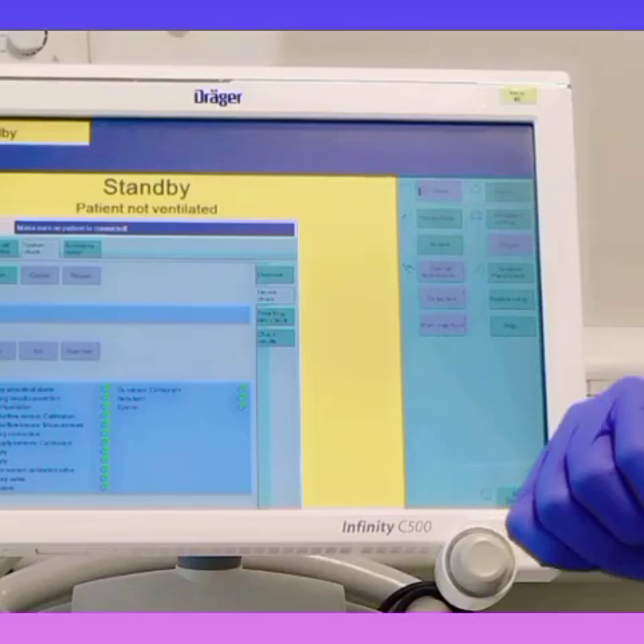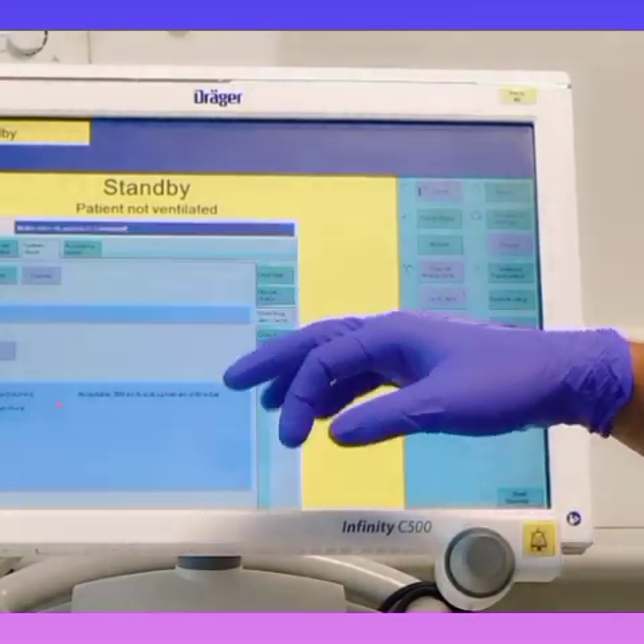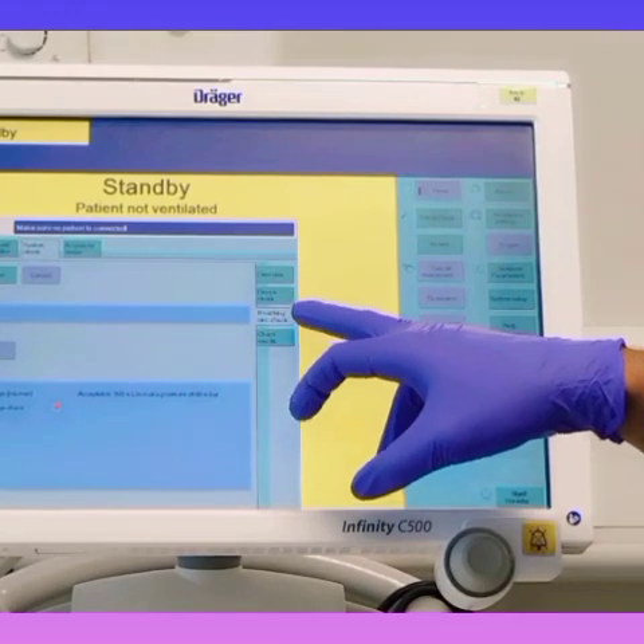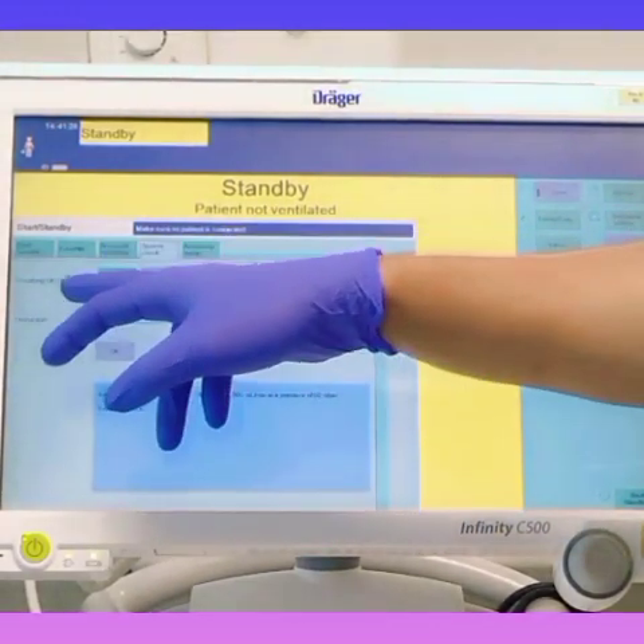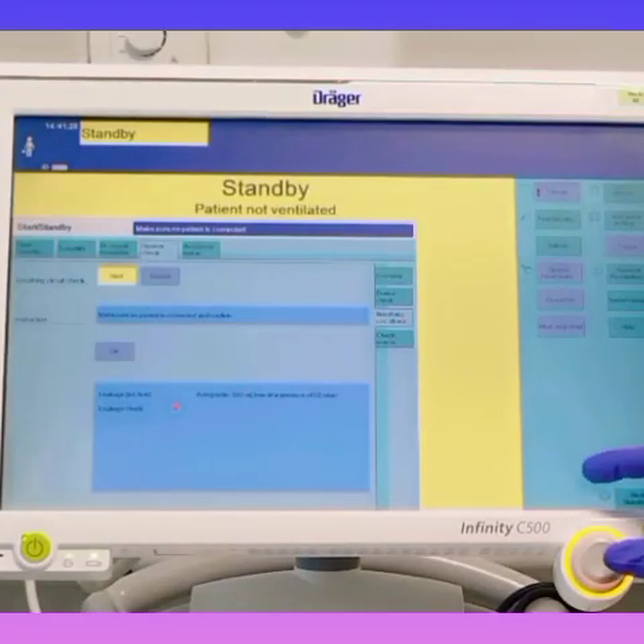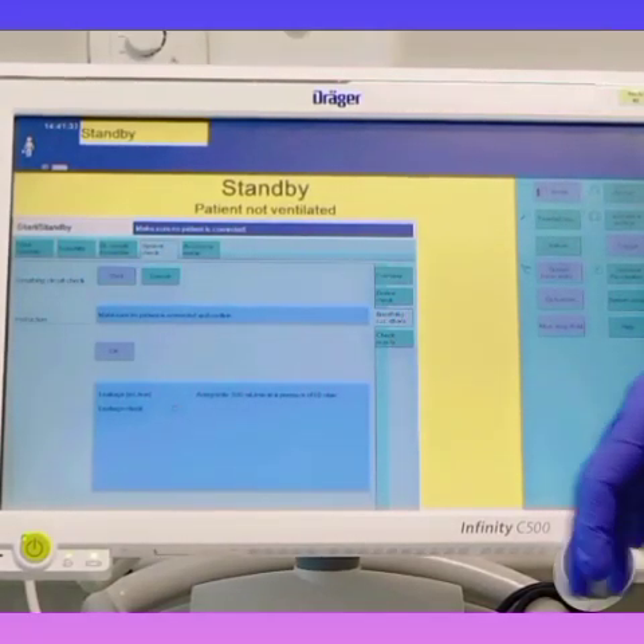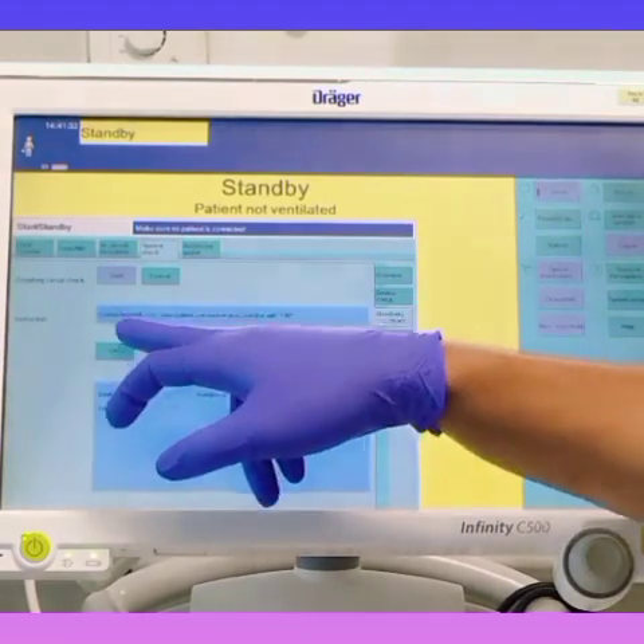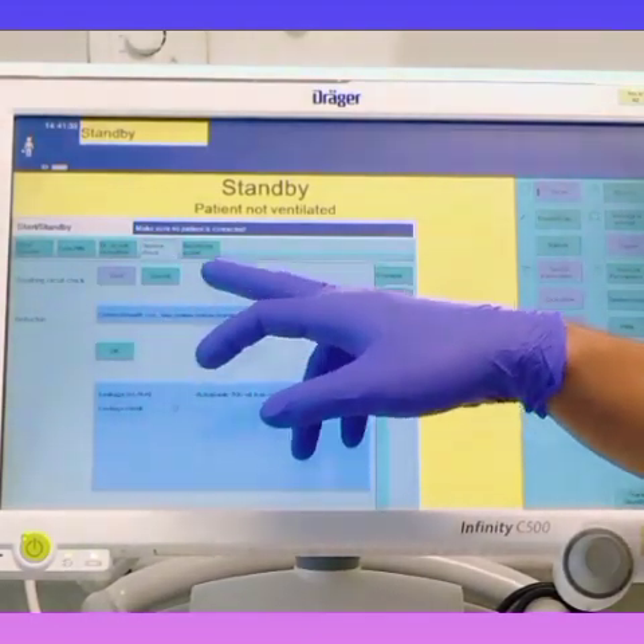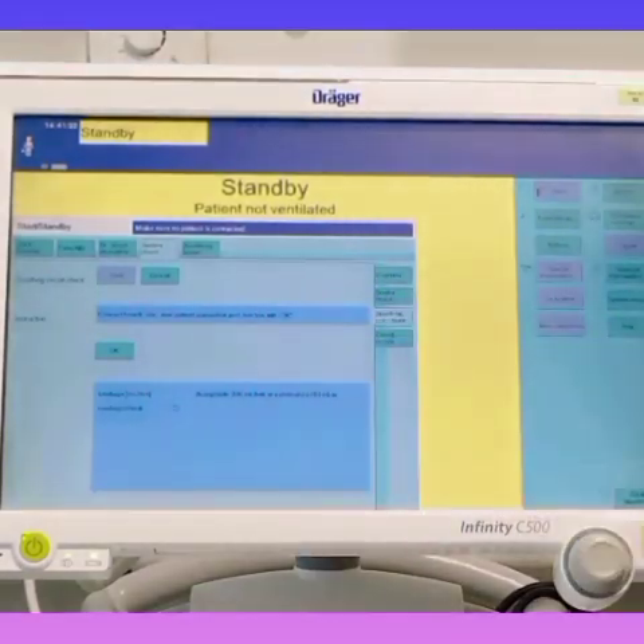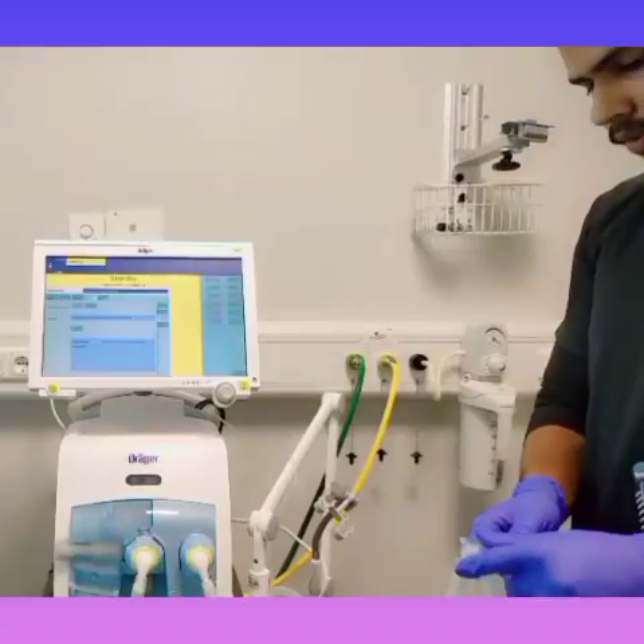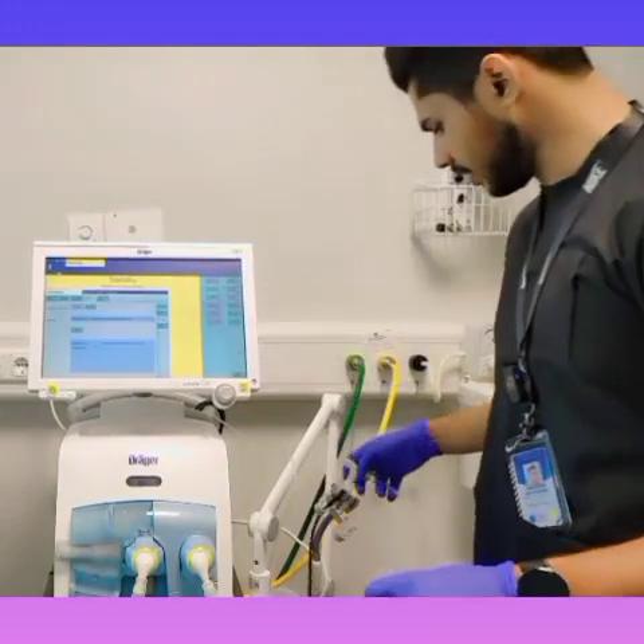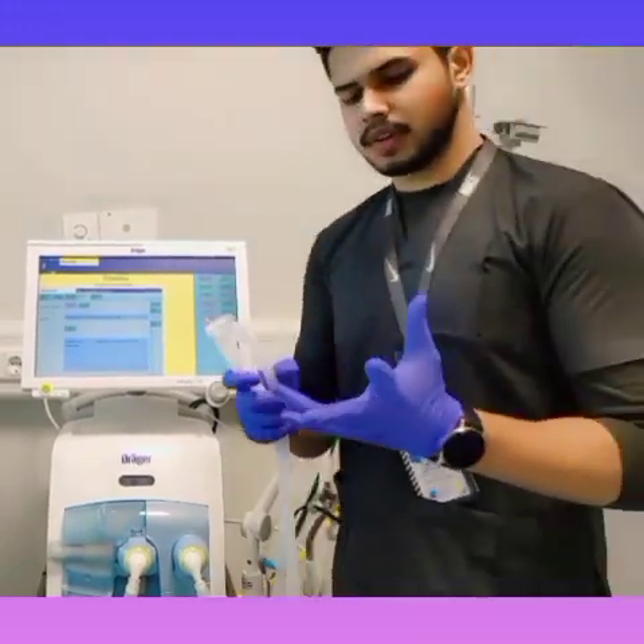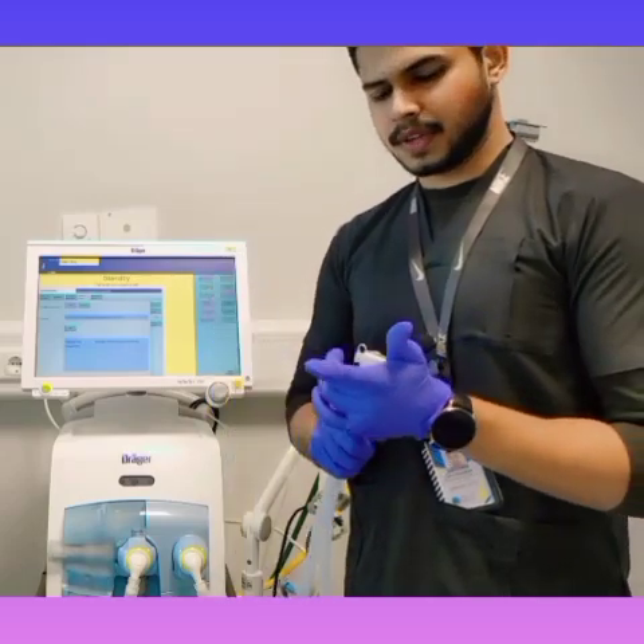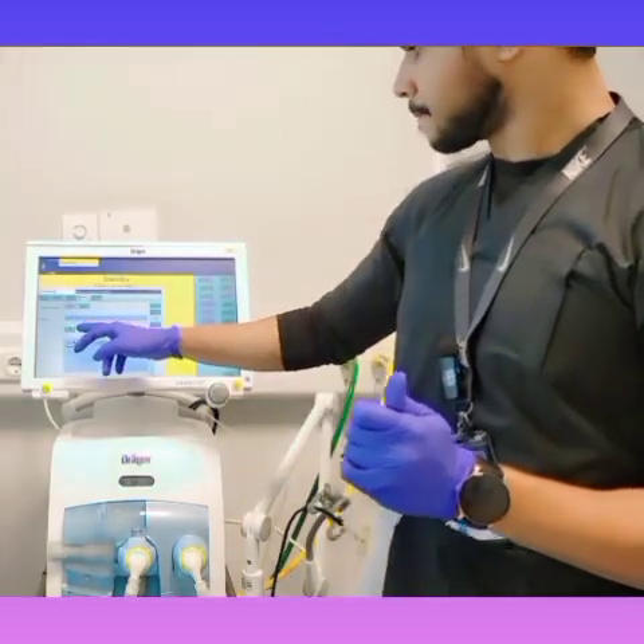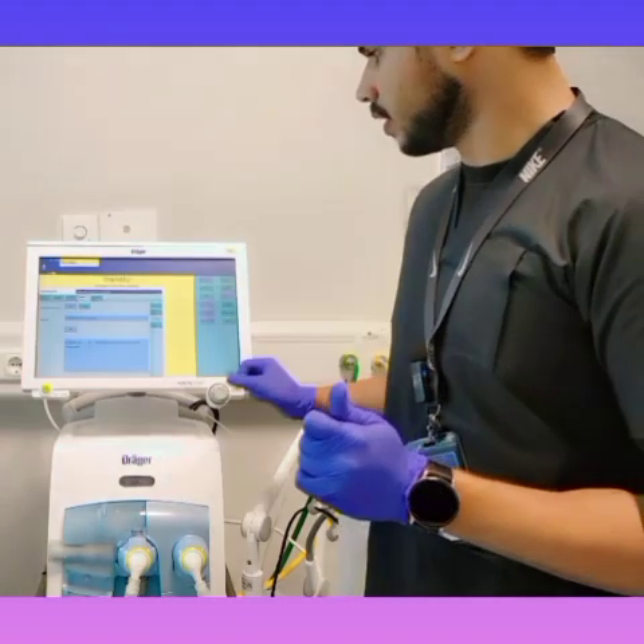The last step for the calibration is the breathing circuit leak test. For that we have to click here, breathing circuit check. Now go to the breathing circuit check start. Okay. Make sure no patient is connected. Connect breathing circuit, seal patient connection port and confirm with OK. We have connected our circuit. We have to remove the flow sensor and test lung, and we have to seal the patient connection port. After that, confirm OK.